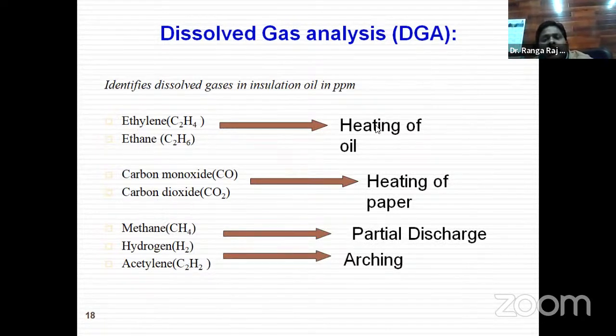The above two gases are generated due to heating of the oil. Even a rise of 10 degrees centigrade in oil temperature produces these gases immediately. If the paper is heated due to overload conditions of the transformer, we find carbon dioxide and carbon monoxide, released from the paper, not the oil. By detecting these two gases through this test setup, we can find the health status of the paper as well. We are not performing a direct test on the paper, but we can get that information from oil analysis.